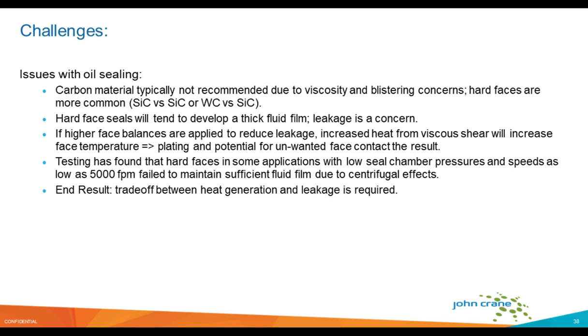Well, hard faces tend to develop a thicker fluid film just because of the finishes and the requirements of those two tribological pairs of materials. So with thicker fluid films, leakage becomes a concern.